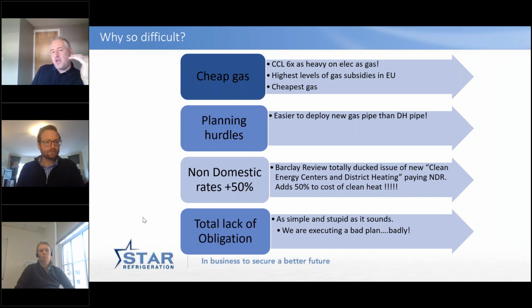I think the point is, if you put it in and it runs at 80 this year, and you manage it the best you can, maybe using something like a mini BMS, you get it down to 75 on many of the days, and it can flex back up to 80 for that one day of the year that's -3. But if at subsequent points they can do stuff to the buildings and get them down, then it gets better. That's what I was saying about the beauty of a heat pump: you put it in and it's got an efficiency. You run it better, it's got a better efficiency.